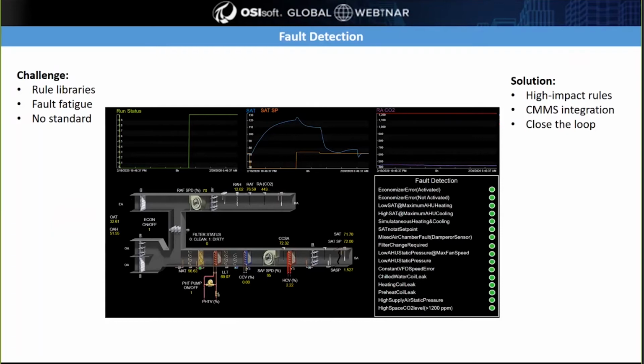So looking at the air handler here, and it's really just to represent fault detection, but there are hundreds of different rules available for an air handling unit like this. We've got return air, exhaust air, outside air, dampers, coils, fan, and some other sensors. So there's literally hundreds of different rules we could apply to an air handling unit like this, but we really don't need to. And I'm just going to talk to you about some of the rules that are valuable, and then maybe some of the rules that are less valuable, just to illustrate and demonstrate that fact.